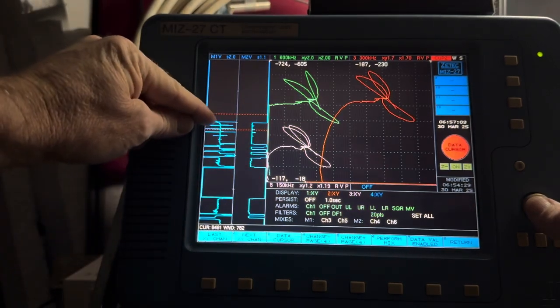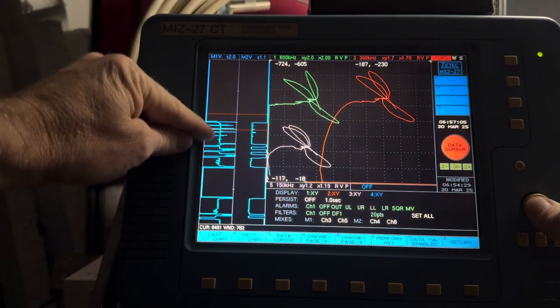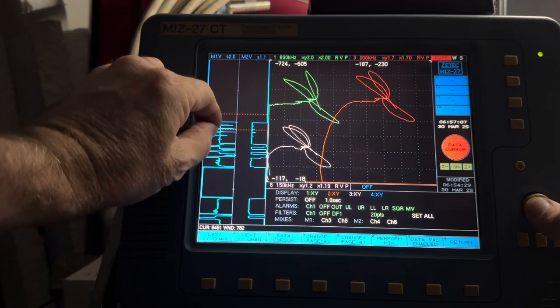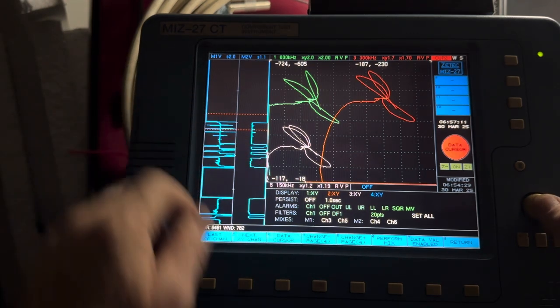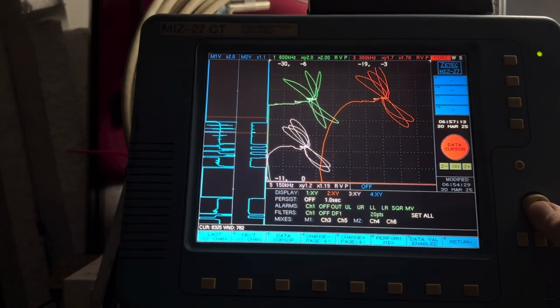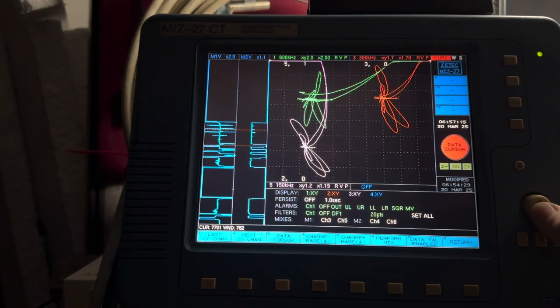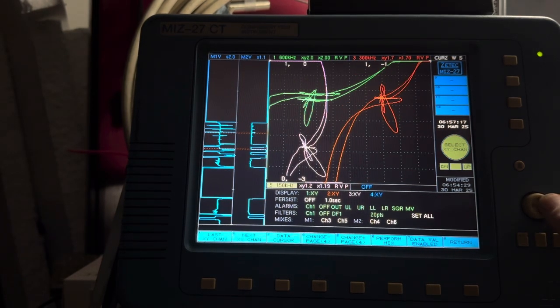So the short pits or the flat bottom holes have a short distance or short time. And then these wider signals are the 1 inch wide wear scars. So for this case, we know that signal amplitude tells you something about the volume of metal that's missing.